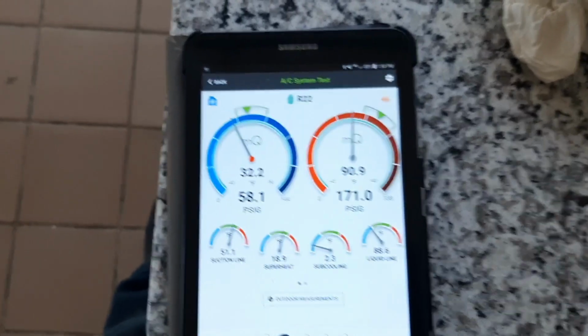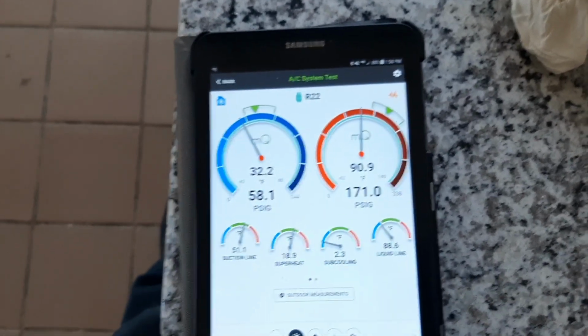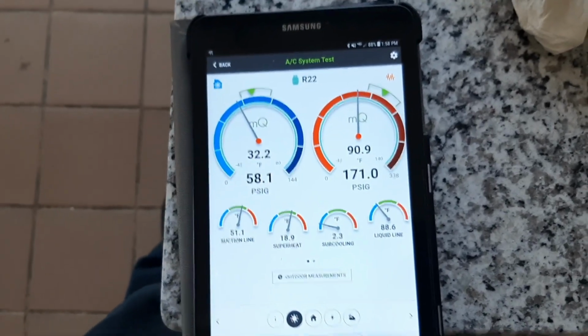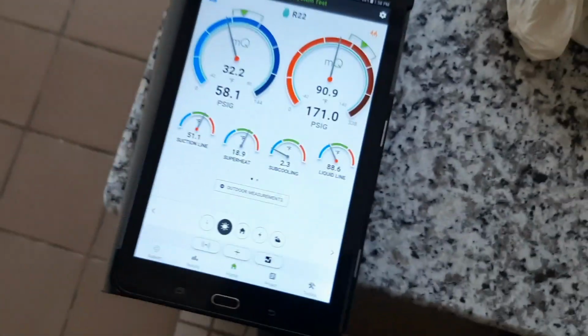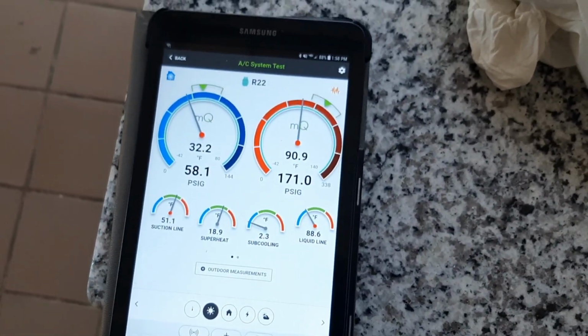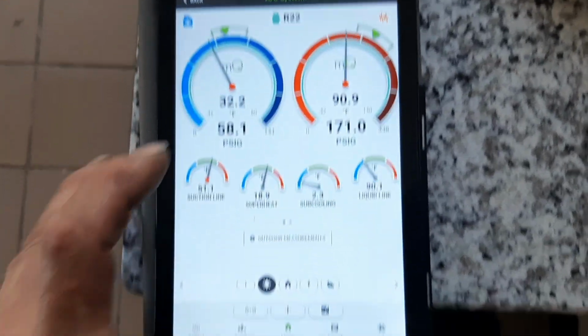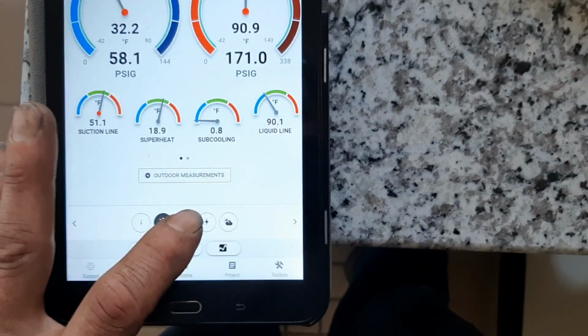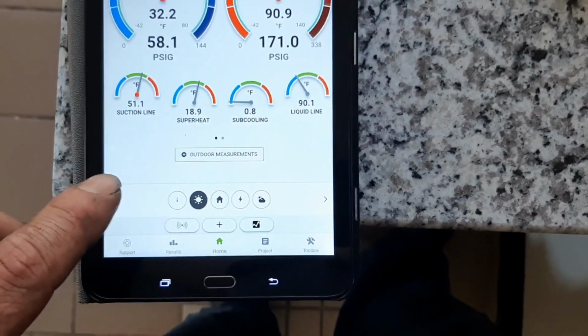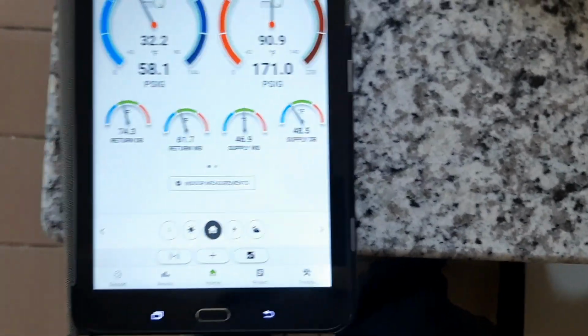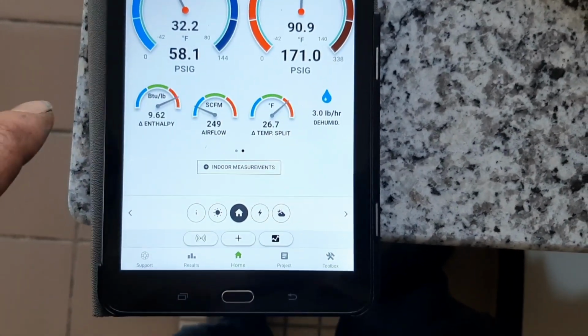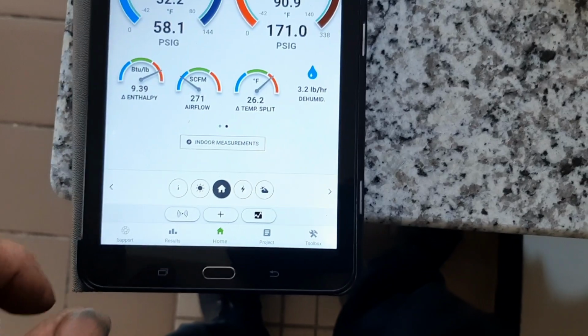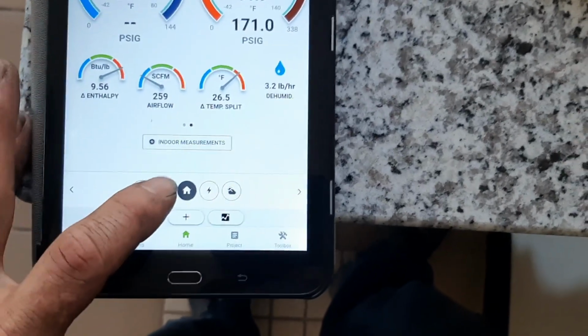Lord, we're looking. None of this is going to be great. It's probably a little low on charge on this one. These are the old R22s, and we've got airflow issues, but it's cooling. Probably needs a shot of refrigerant. We're not going to do anything to it just yet. We'll let them know what they got, because the evaporator's probably leaking. I didn't see any oil outside, and that temp drop again, 26 degrees. So we know we got issues here.